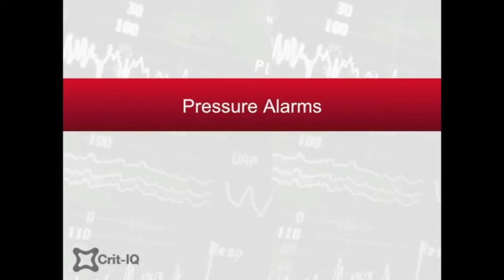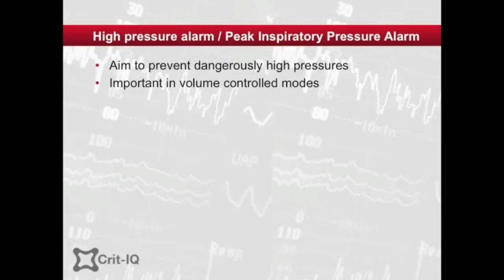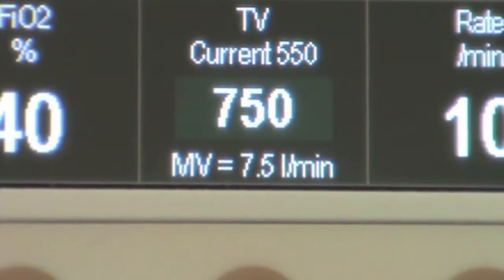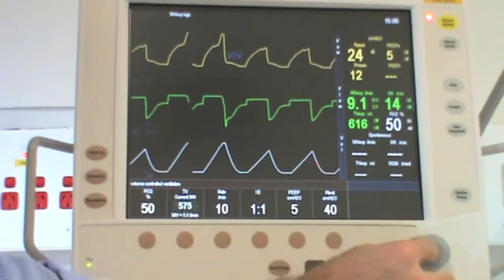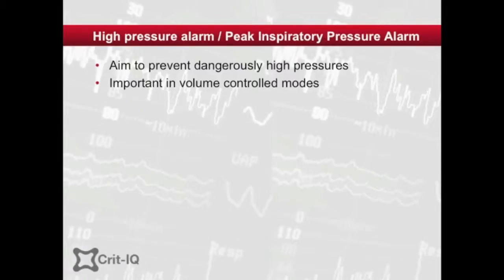Two of the most important alarms on the ventilator are the low and high pressure alarms. The aim of the high pressure alarm is to detect and prevent dangerously high peak pressures, with the intention of minimising pressure-related lung injury. This is of most relevance in volume-regulated modes of ventilation, where the pressure generated is dependent on the volume selected and the resistance of the circuit and airways. Pressure-controlled modes, by definition, are limited to the inspiratory pressure set.